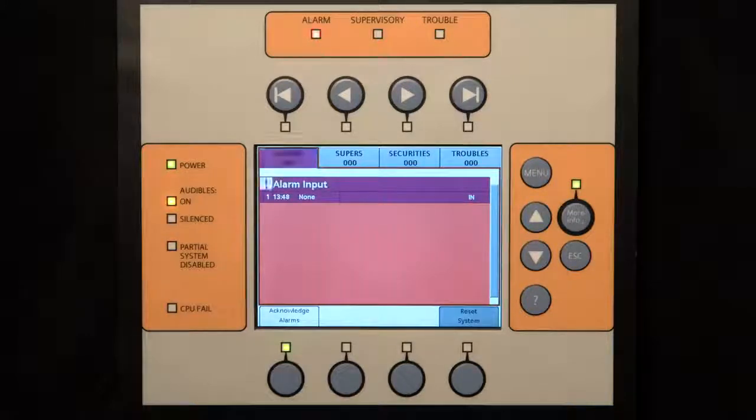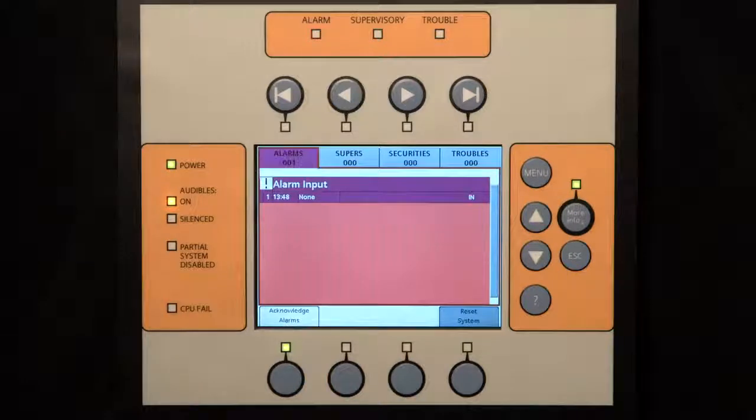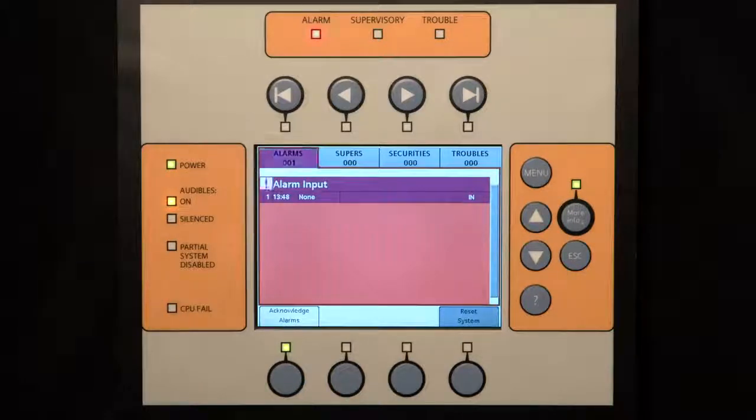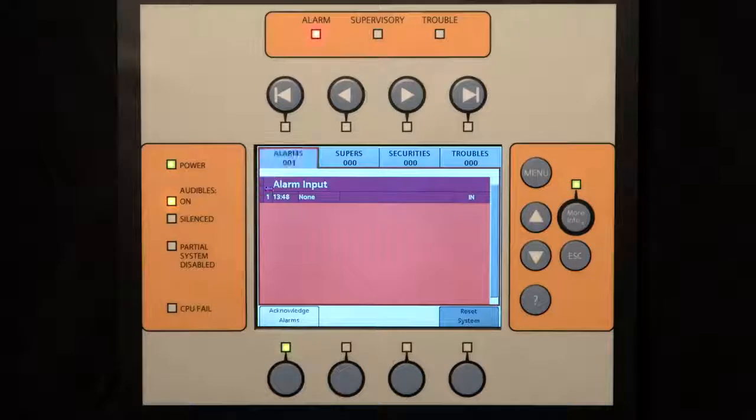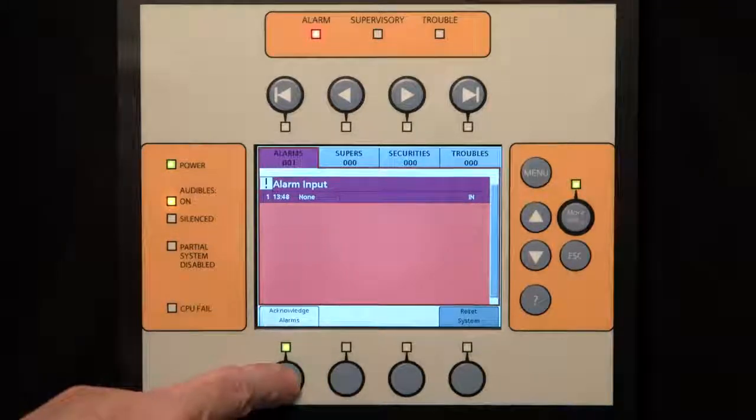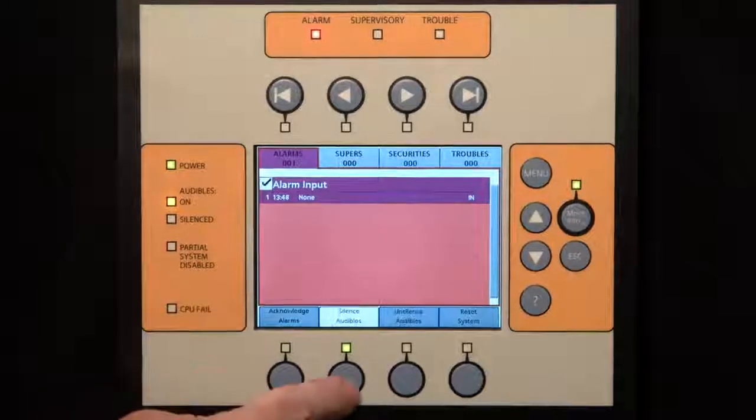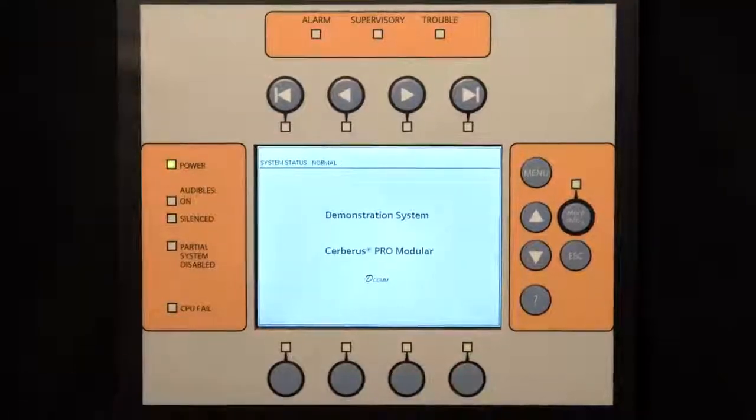While not visible, the buzzer lets the user know there is activity within the modular system. The buzzer will sound steady when an event is unacknowledged, and will pulse when it is acknowledged in supervisory or trouble conditions exist. When all conditions are acknowledged, the buzzer will be silent.